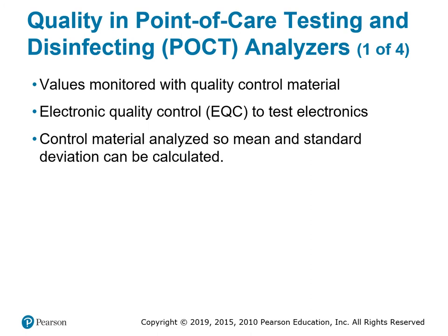Quality in POC testing and disinfecting POC analyzers: values are monitored with quality control materials. Electronic quality control, or EQCs, test the electronics. Control materials are analyzed so mean and standard deviations can be calculated. All right, now to understand what's going on here, think back to math where we studied the mean, median, and mode.